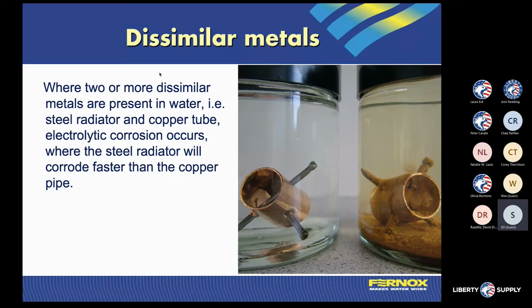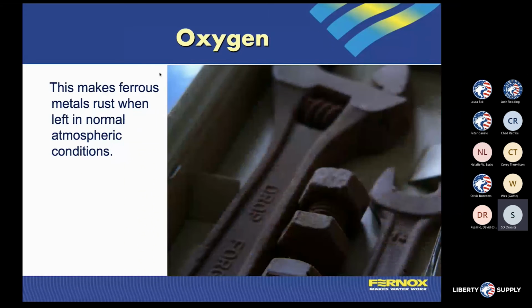So we're going to really start to focus on how we're going to balance and maintain that system so we don't have breakdown of all the different materials. We're going to try to add that inhibitor to protect our system from breaking down any further. Obviously, on top of that, if we add oxygen to the system, most hydronic systems are pressurized, which means we're going to remove all the oxygen out of solution and try to get that out of the system.